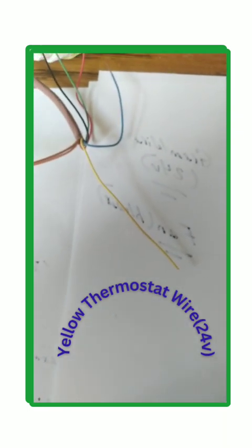What is the yellow thermostat wire used for in HVAC use? Simply, we have addressed the blue and the red. The blue and the red pull the 24 volts in. So once 24 volts has been pulled in to the thermostat, what function would the yellow be? 24 volts is passed from the red to the yellow via the thermostat according to what is called.